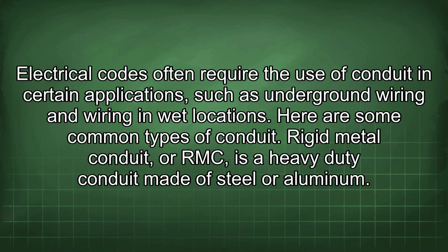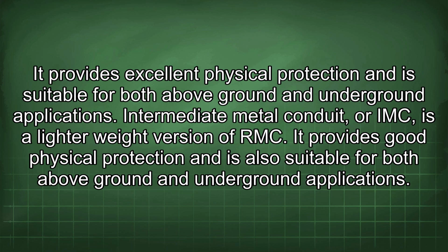Rigid metal conduit, or RMC, is a heavy-duty conduit made of steel or aluminum. It provides excellent physical protection and is suitable for both above-ground and underground applications. Intermediate metal conduit, or IMC, is a lighter-weight version of RMC. It provides good physical protection and is also suitable for both above-ground and underground applications.